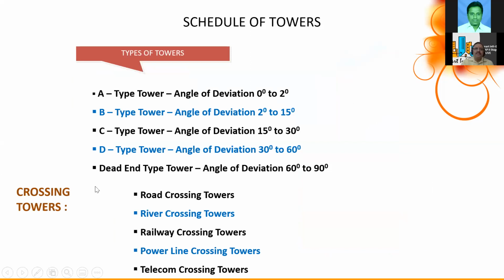B-type tower is small angle tower or tension tower. C-type is medium angle tower or tension tower again, 15 to 30 degrees deviation - meaning the line deviation will be 15 to 30 degrees. And dead end tower or large angle tower - dead end and large angle are combined many times.